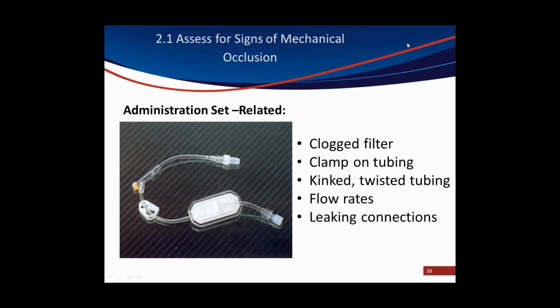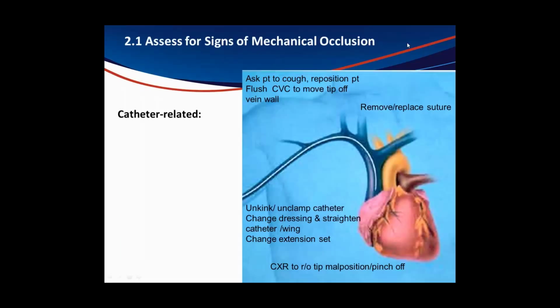You also want to look for signs of the administration set causing the occlusion. Maybe it's related to the catheter. And so, of course, the first thing you're going to do is look at the catheter site. If there's clamps on the catheter, check to make sure that they are unclamped. Is that catheter kinked? Especially our PICCs are such a fine diameter. If that catheter is twisted, that can cause an occlusion. And you may need to change that dressing and make sure that the catheter is lying straight on the skin with no kinks or twists.